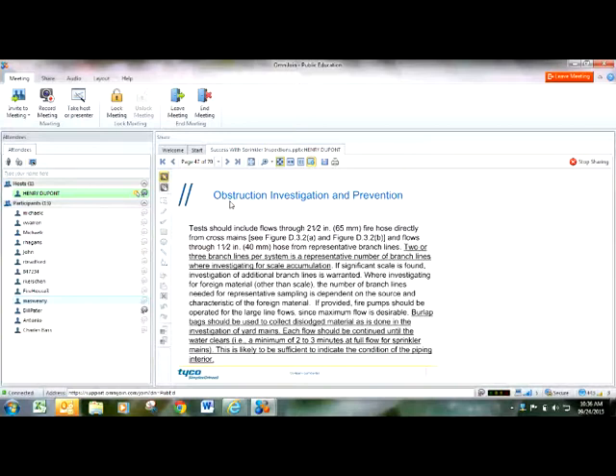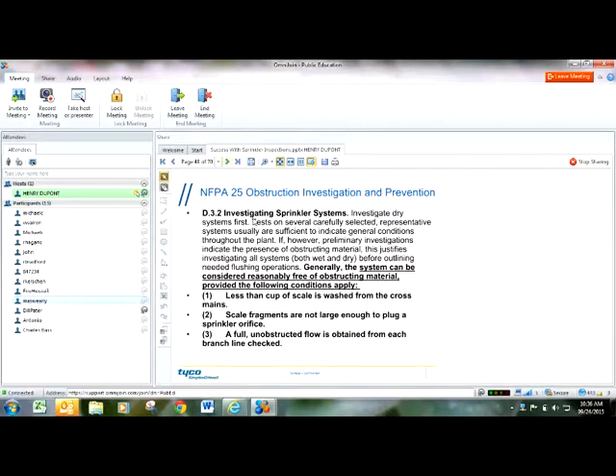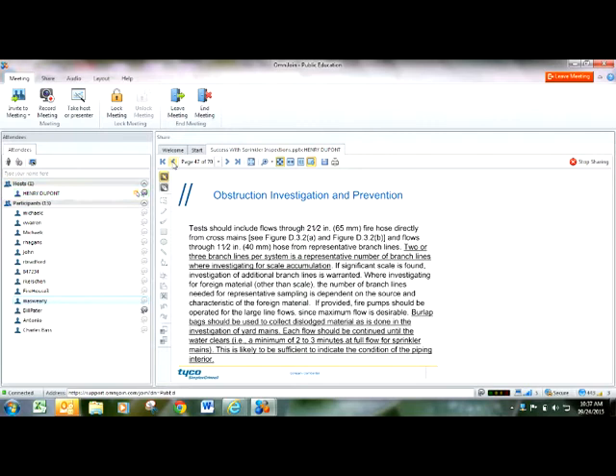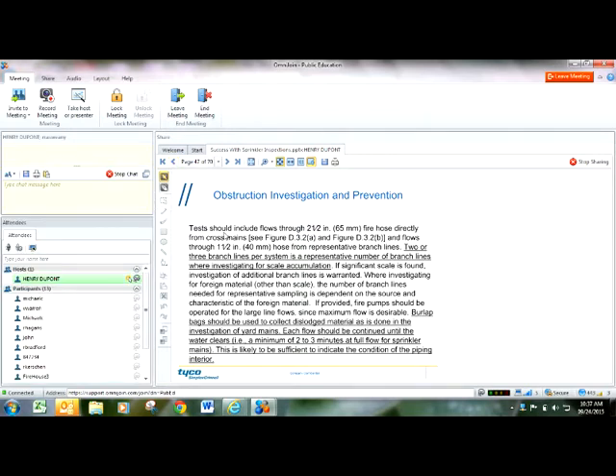We'll flush those branch lines and mains, and we'll capture what comes out through burlap bags. If what comes out of those burlap bags is less than a cup of scale, the scale fragments aren't large enough to plug a sprinkler head, or full unobstructed flow is obtained, then you can say that system is reasonably free of obstructing material and consider it okay. If you don't get that, then you have to do a full flushing investigation. That's where you flush every sprinkler branch line and every sprinkler main. And this is what tells you how to do that.